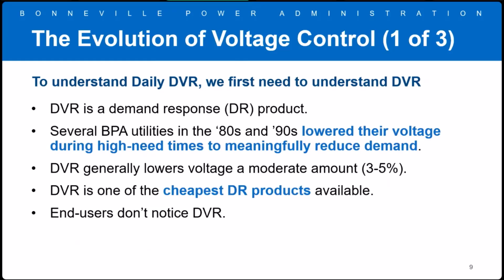Voltage control products started many decades ago with demand voltage reduction, or DVR. This was initially a demand response product, and BPA utilities as far back as the 80s and 90s had been lowering voltage during times of high need to reduce demand. This approach generally lowers voltage a modest amount, between 3 and 5%, and it's one of the cheapest DR products available. End users, unlike with many other DR products, simply don't notice when you implement it. This is a long-standing method utilities have used to address voltage needs for many decades.